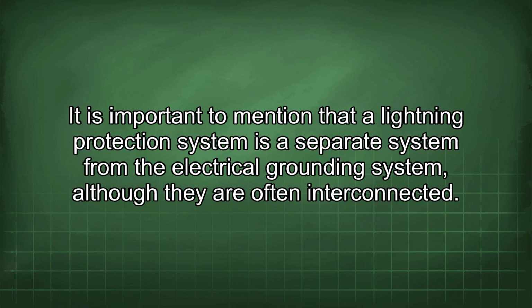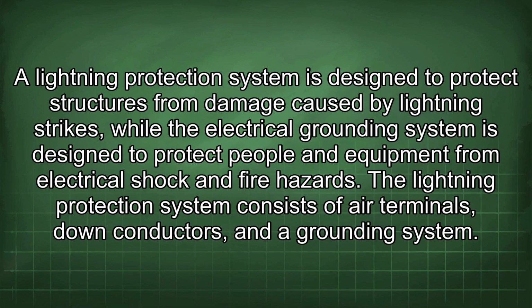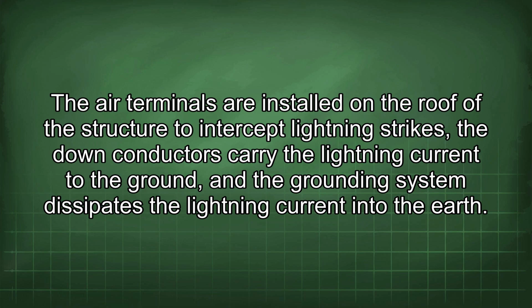It is important to mention that a lightning protection system is a separate system from the electrical grounding system, although they are often interconnected. A lightning protection system is designed to protect structures from damage caused by lightning strikes, while the electrical grounding system is designed to protect people and equipment from electrical shock and fire hazards. The lightning protection system consists of air terminals, down conductors, and a grounding system. The air terminals are installed on the roof of the structure to intercept lightning strikes. The down conductors carry the lightning current to the ground, and the grounding system dissipates the lightning current into the earth.